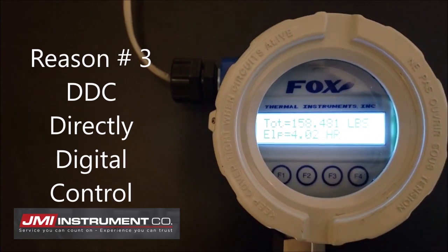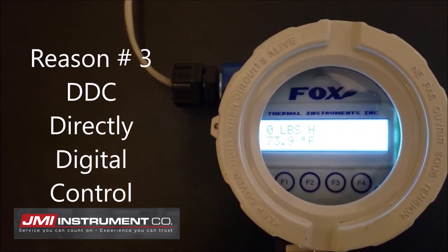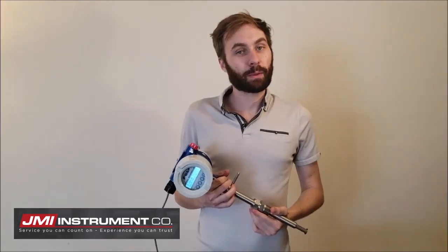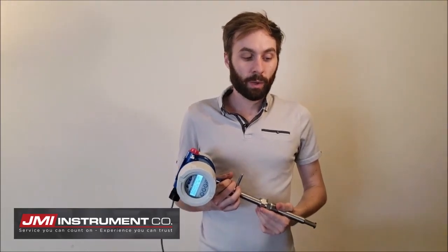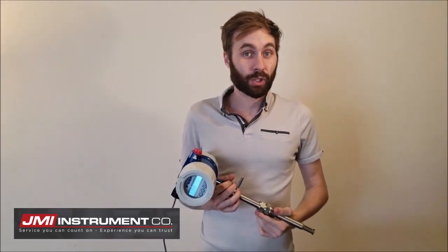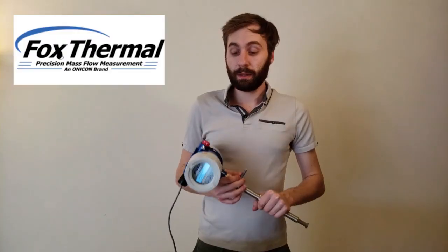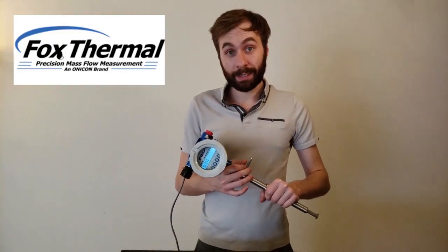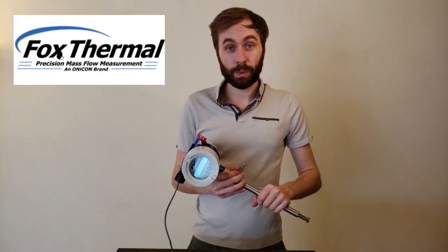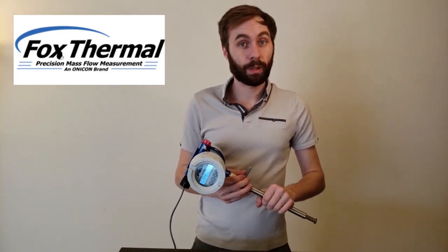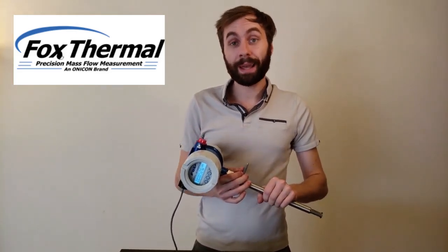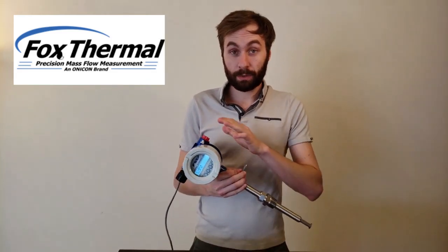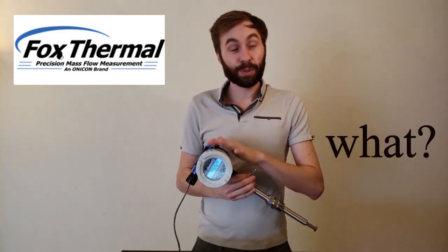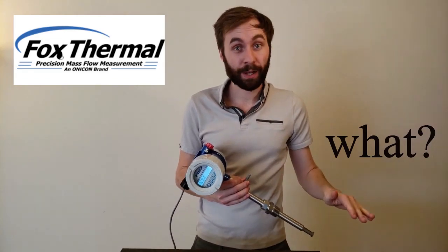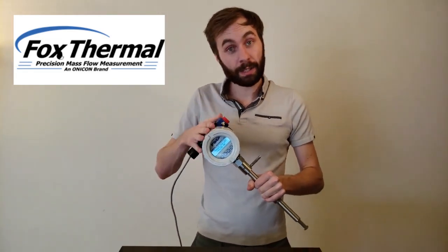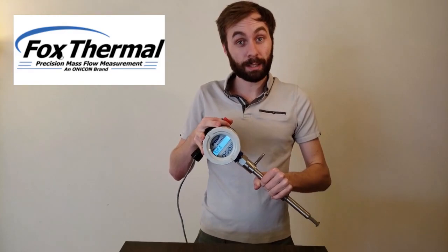Reason number 3, DDC, directly digital control. So the third and final question I have for you, what do you do when your gas composition changes in the field? Fox Thermal's DDC, the directly digital control, allows you to do 2 things you've never been able to do before. You can adjust your gas flow and your gas composition reading directly in line. You don't have to take it out. You don't have to go to the factory. You can do it directly in here, in the directly digital control, in the sensor.